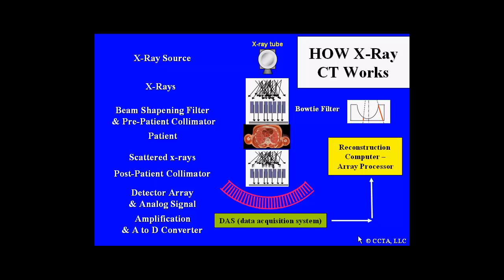Once the x-rays leave the patient, they are also scattered and are sent through a post-patient collimator, which also determines individual slice thickness. This information is then incident upon a detector array, which produces an analog signal from the photon energy. This information is then amplified and sent from analog to a digital converter called the data acquisition system or DAS. Once this digital information is available, the data are then sent to a reconstruction computer called an array processor.